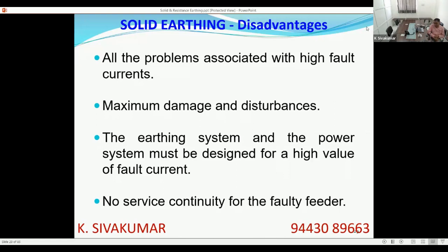And the system should be designed for the high value of fault current. The earthing conductor, the earth fault interconnecting equipotential bonding conductor, earthing conductor, protective conductor, everything has to be sized for the high value of earth fault current. And the faulty feeder, compared to an ungrounded system: in an ungrounded system, the faulty feeder will not be disconnected. If you make a one-to-one comparison, service continuity of the faulty feeder will not be there because it gets tripped.